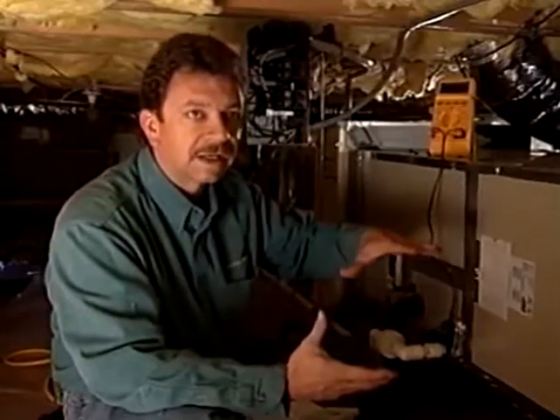For heat pumps, the number you get should be within 5% of 400 CFMs per ton of cooling, or the manufacturer's specifications for the particular equipment. If you have too much CFM, what you would like to do is slow the fan speed down by dropping to a lower speed tap, or if it's not enough CFM, you would increase the speed by going to a higher speed. If you do have too much airflow and you cannot drop it any lower, what you'd have to do is put some type of damper over the squirrel cage fan inside to slow it down even more, to get a more accurate reading.